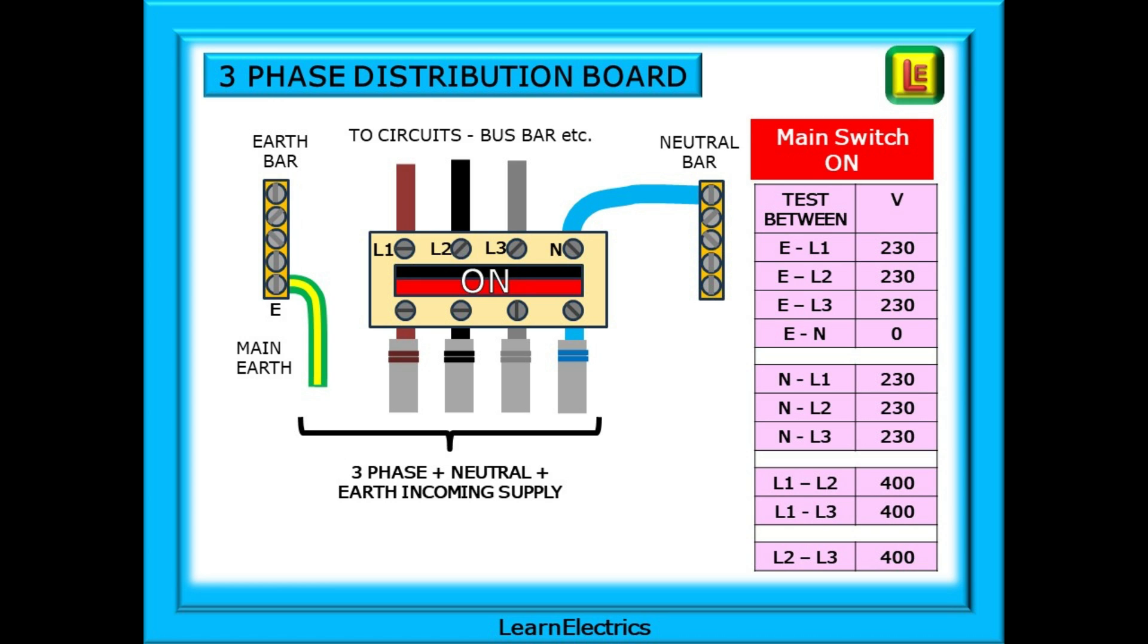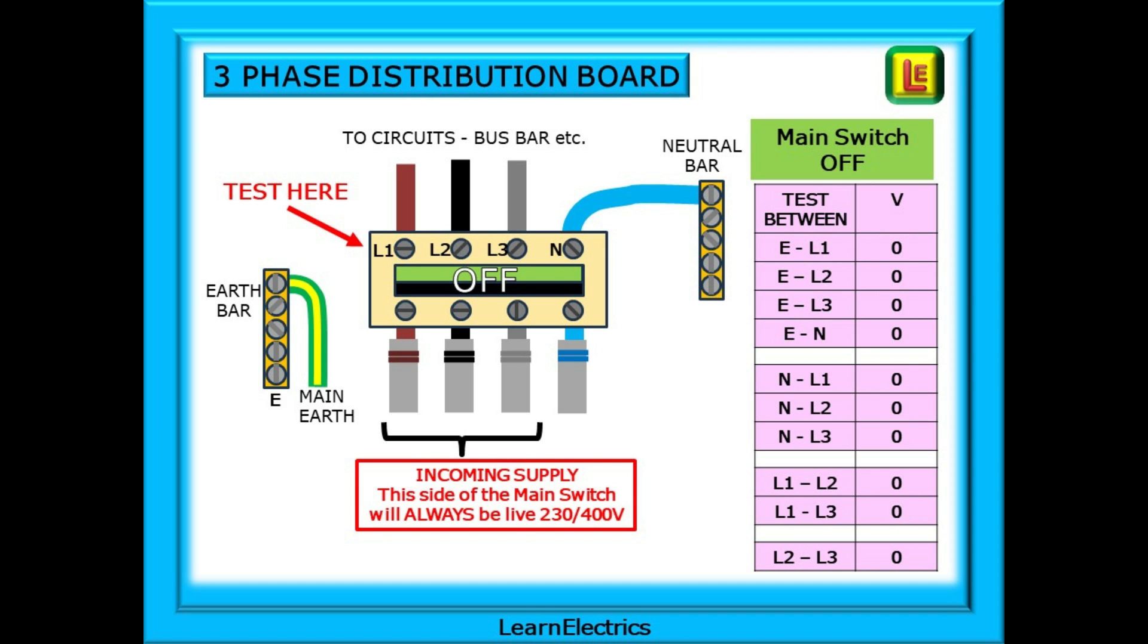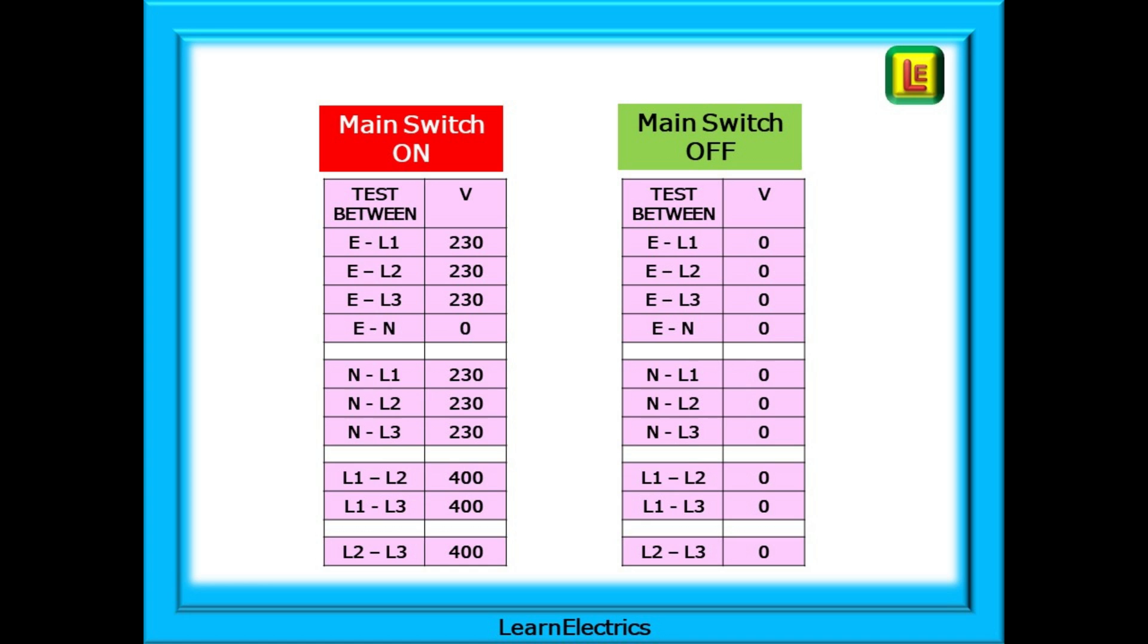If we turn the main switch off, what happens to the voltages? Remember, we are testing at the consumer side of the switch. In this drawing, we are placing our test probes in the top row of terminals plus the earth bar. With an isolated installation, all ten voltage checks will return zero volts. Make sure that you are testing on the consumer side, the switch side, of the main switch. The incoming feed or supply will always be live at 230 volts or 400 volts. A comparison of the two voltage charts side by side is given here. With the main switch off, all voltage checks will be zero volts and we can consider the installation isolated. Always remember to retest your meter for correct function after safe isolation checks. If a probe has become disconnected, you will read zero volts even on a live circuit. It does happen and you need to know. It's your safety on the line.